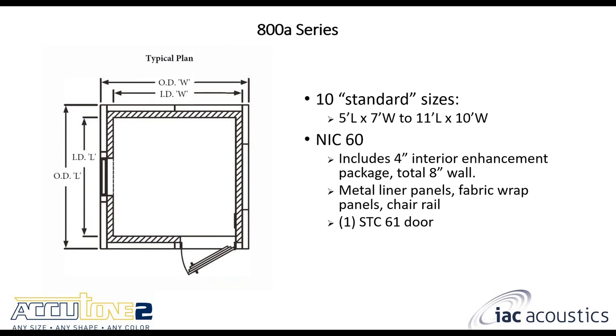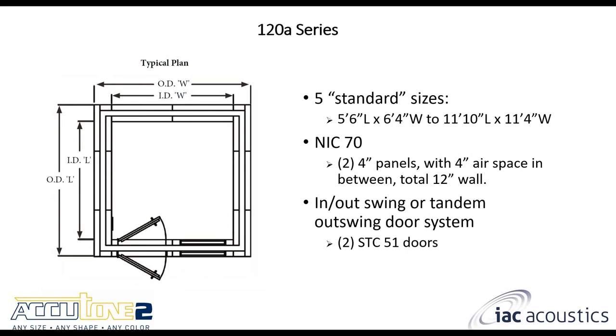The 800A series achieves NIC60 performance by combining a four-inch wall panel with a four-inch interior enhancement package for an eight-inch thick wall construction. It includes a metal liner panel, fabric panel, and chair rail covering the joint. The door upgrades from STC51 to STC61 — a three-and-a-half-inch thick door — and the wall panel construction increases to what IAC calls a Noise Lock 7.